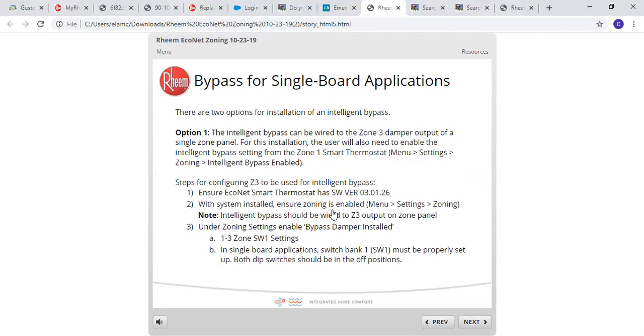So with system installed, ensure zoning is enabled. Menu, settings, zoning, and then note the intelligent bypass should be wired to Z3 on the zone panel. Under zoning settings, enable bypass damper installed. Zone SW1 settings: in a single board application, the SW1 must be properly set up, and both dip switches will be set in the off position. One board, dip switches are always in the off position.